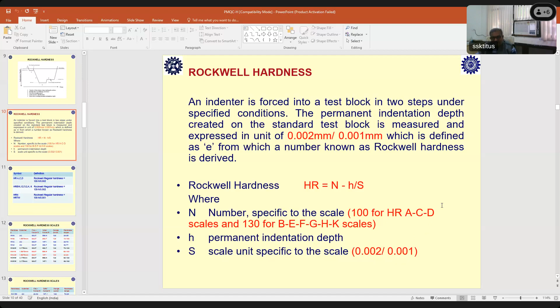So 90 HRB here. H is the permanent indentation depth, and the scale unit is either 0.002 for the Rockwell A, B, C scales, and there is one more thing I have mentioned here, 0.001. This is for the superficial scale. For superficial scales, we have to divide it by 1 micron, because that is still softer material. So this is how the entire Rockwell hardness scale is derived.